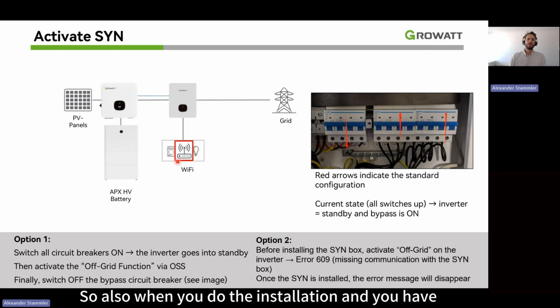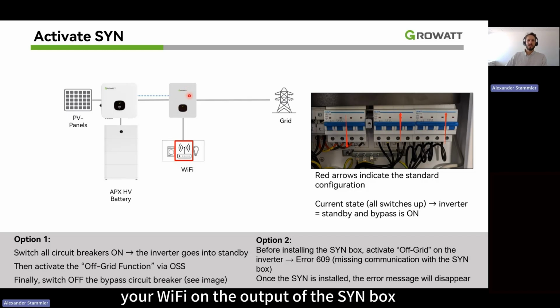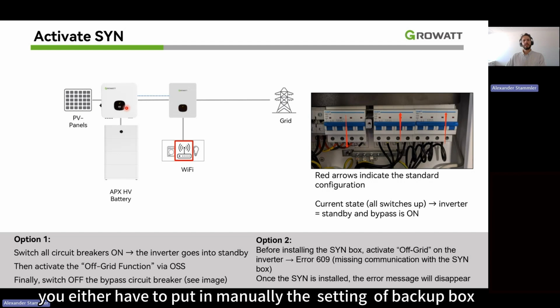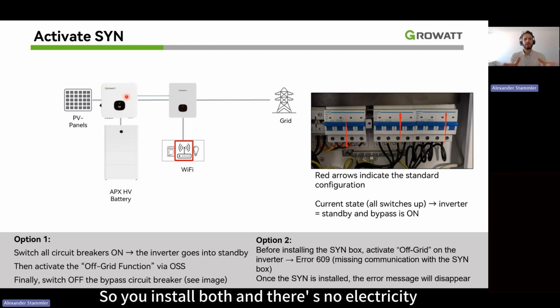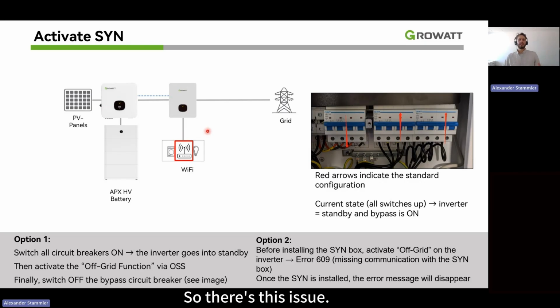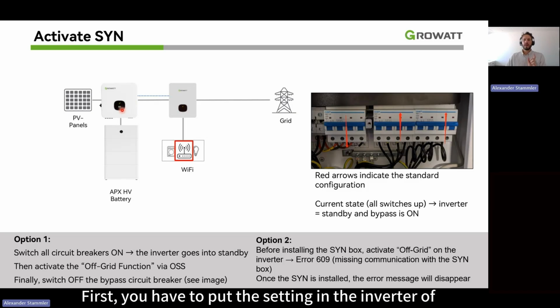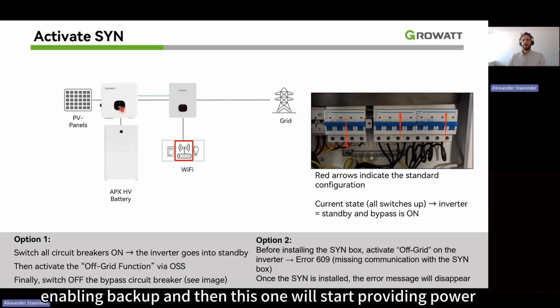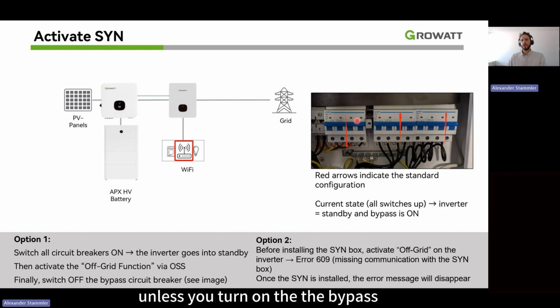Also, when you do the installation and you have your Wi-Fi on the output of the SYN box, you have to put in manually the setting of backup box. If you don't, you install both and there's no electricity, because you didn't do any setups. This means the inverter doesn't know that you have a backup box, so they don't communicate. That means this one will not provide energy. So you have to put the setting in the inverter of enabling backup, and then this one will start providing power. Unless you turn on the bypass, then the power will just go through, and then you can do the setting on the inverter.